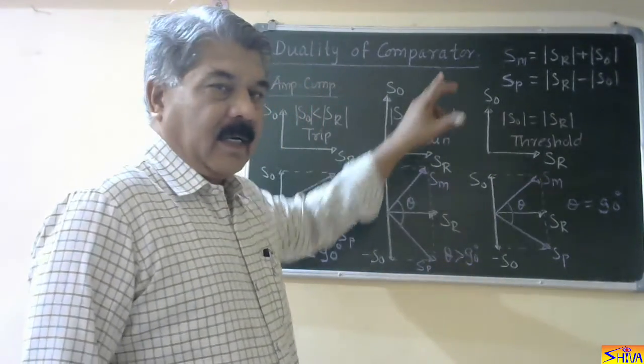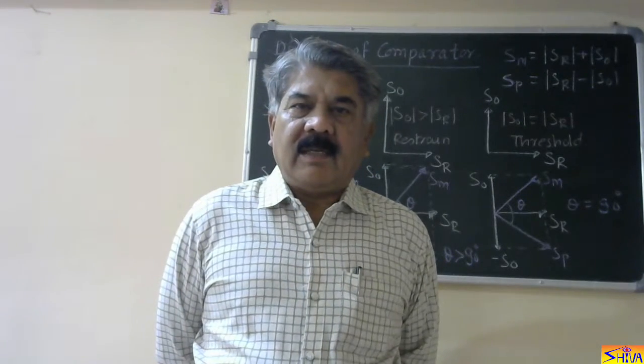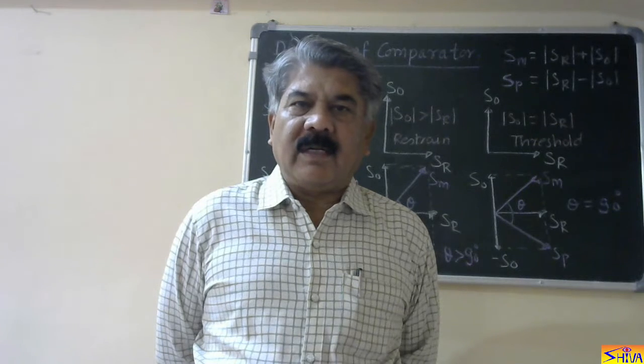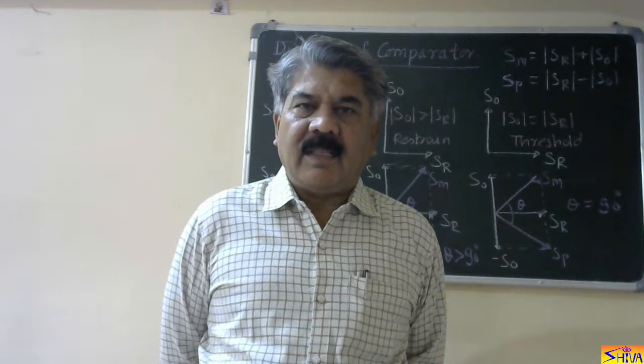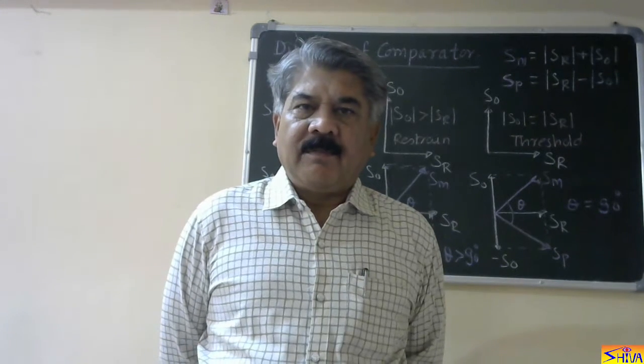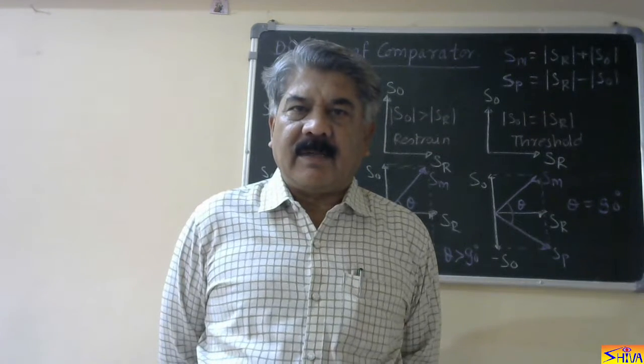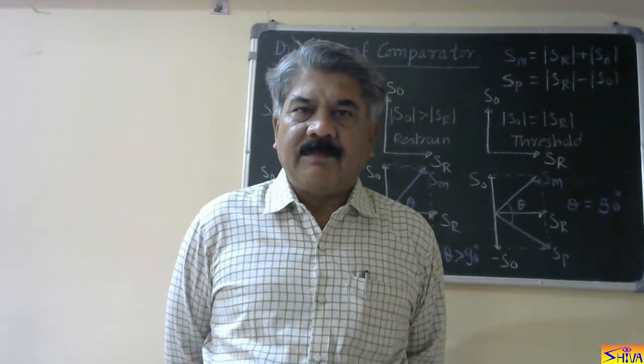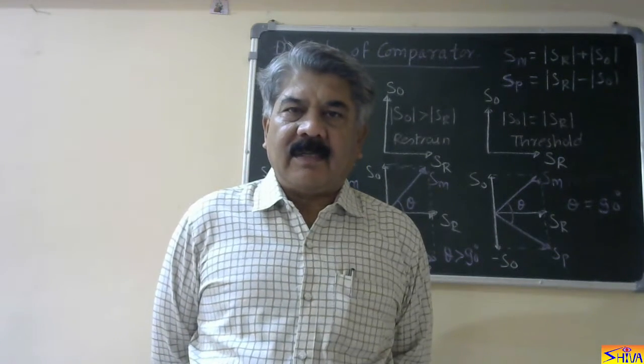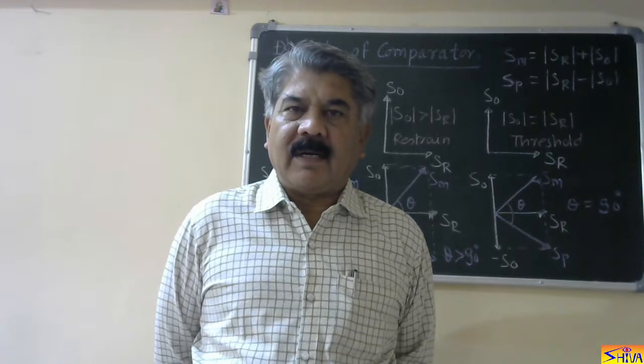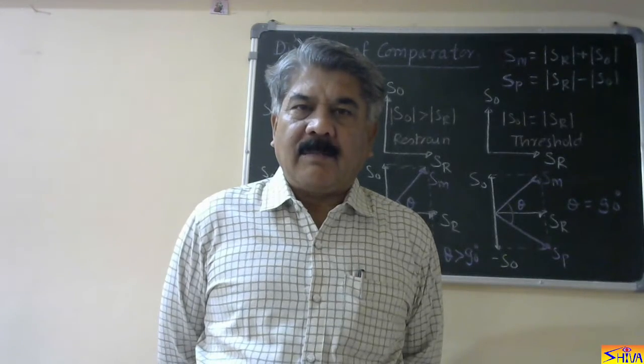Duality of the comparators states that if we change the input quantities of an amplitude comparator to their sum and difference and feed them to a phase comparator, then the conditions of the amplitude comparator can be obtained by the phase comparator, and vice versa — if we change the input quantities of a phase comparator to their sum and difference and feed them to an amplitude comparator, then the conditions of the phase comparator can be obtained by an amplitude comparator.